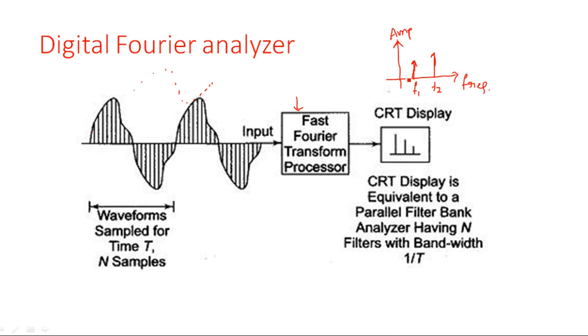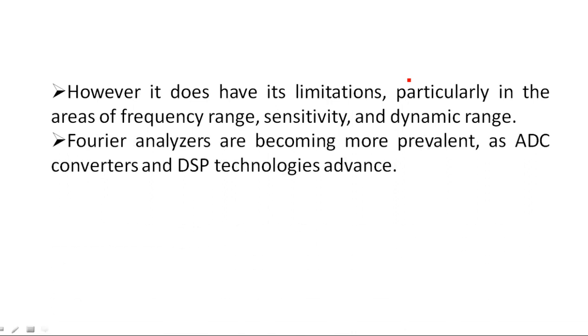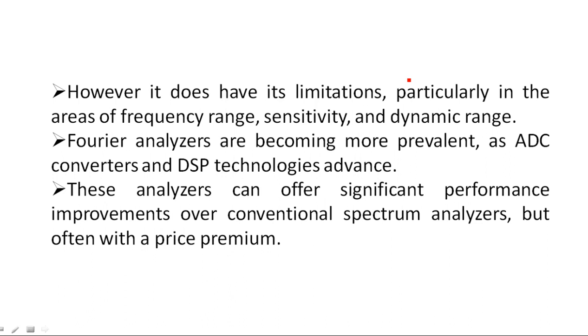Now let us see the complete and detailed block diagram of this fast Fourier analyzer. However, it does have its limitations, particularly in the areas of frequency range, sensitivity, and dynamic range. Fourier analyzers are becoming more prevalent as analog-to-digital converters and DSP technologies advance. These analyzers can offer significant performance improvements over conventional spectrum analyzers, but often with a price premium.